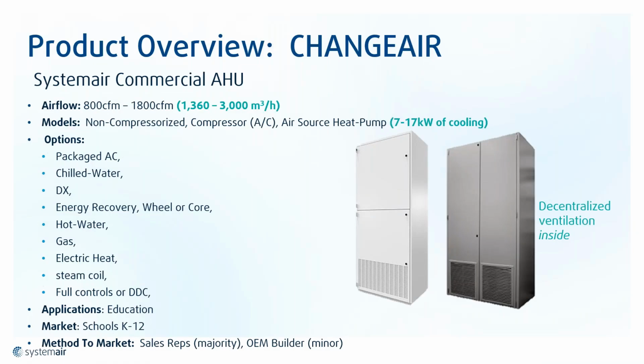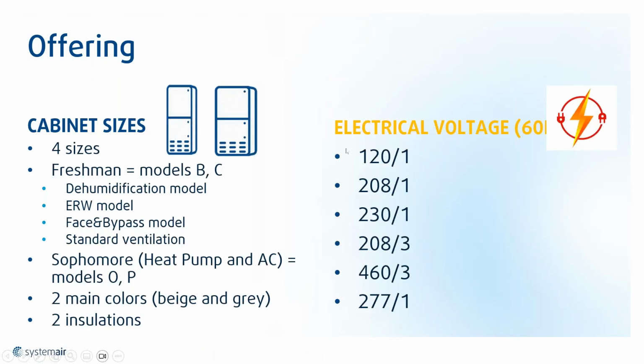And let's get into the design. So the design is what exactly? It's two main series, the freshman, as we call it, without a compressor, and the sophomore with a compressor. They're both decentralized ventilation solutions, and we could provide anywhere between 800 to 1800 CFM. We could even push it a little bit higher with the larger size cabinet of the freshman. And then you get all these options and all these accessories to toy with. So what I'm going to show you next is a whole bunch of offering. And then keep in mind, this is all selectable in our software, and you can mix and match the items you need to get the exact tailor-made or configurable unit for your market, for your school board, for your climate zone.